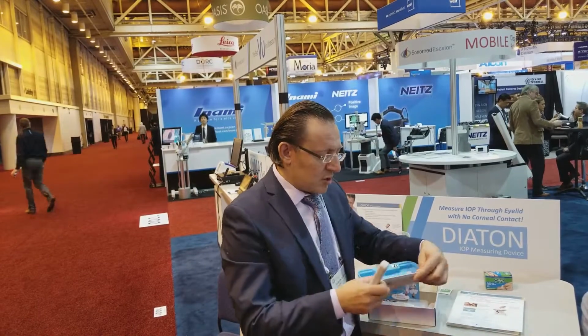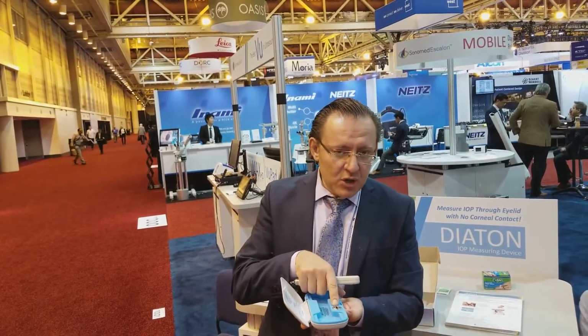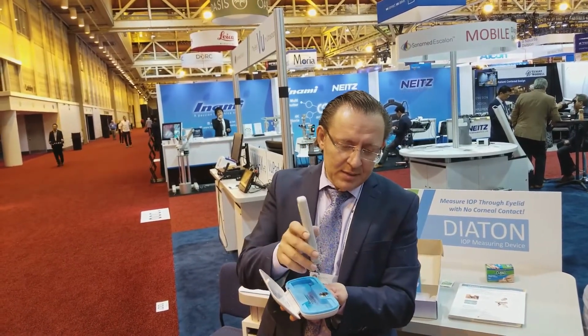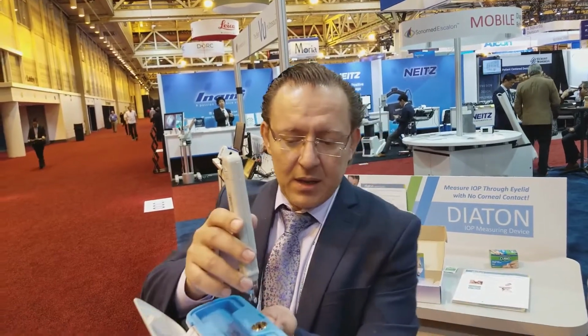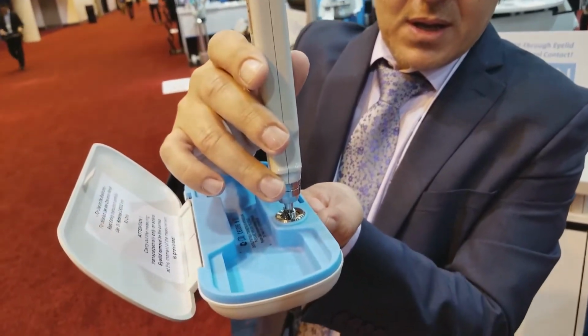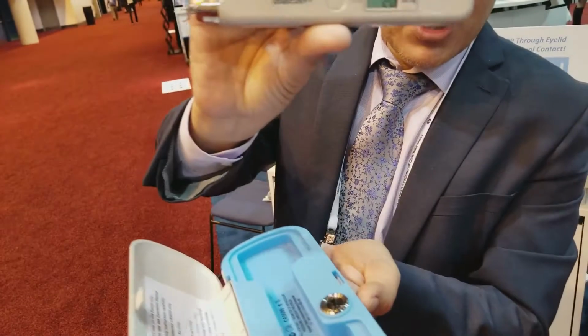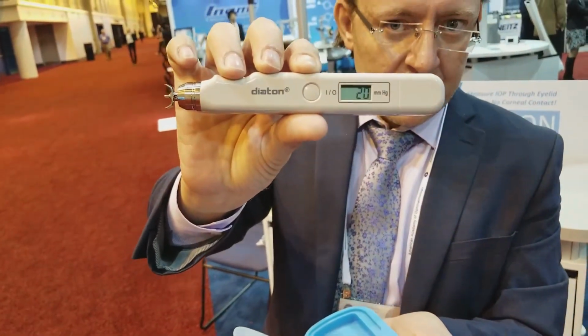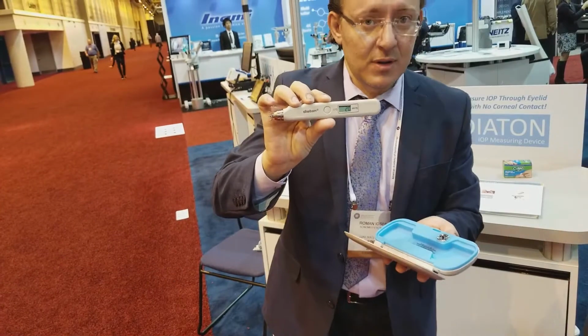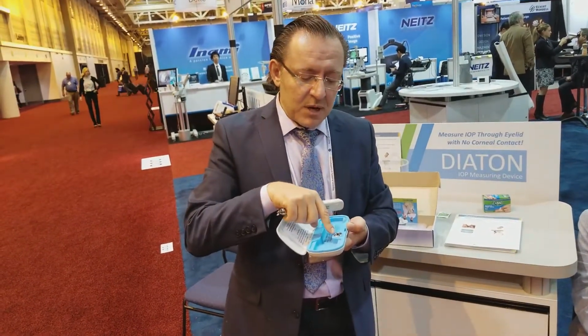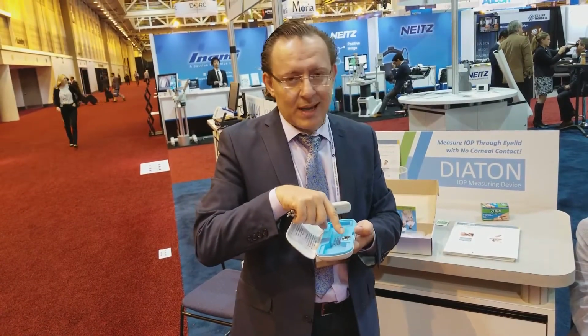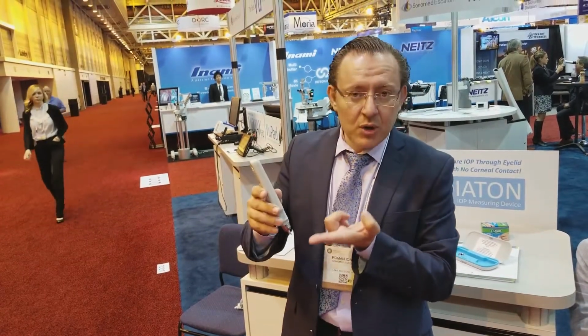Initially, what is suggested to do, on the carry case, there's a calibration tester. The device is pre-calibrated, but it's always good to check the first time you use the device. It has 2 little indents. You could position and take a quick measurement. Okay, it should be plus or minus 1 of 20 on the display. The device is ready to work with. What we do suggest, you could also practice a few more measurements on the actual test eye or the calibration tester. I also strongly suggest to take a few readings on your own finger.